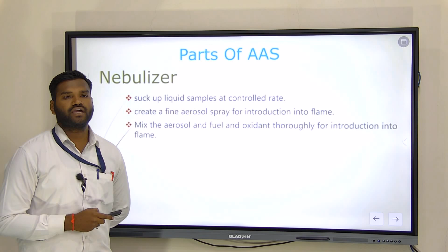Next, it is a nebulizer. It sucks the liquid sample at a controlled rate, creates a fine aerosol spray for introduction into the flame, and mixes the aerosol and fuel oxidant thoroughly for introduction into the flame. This nebulizer is converting the sample into an aerosol.